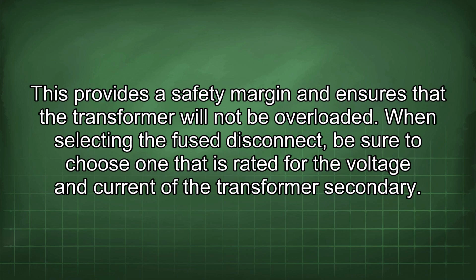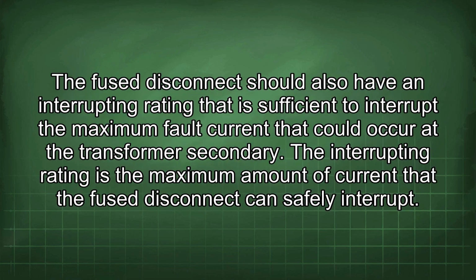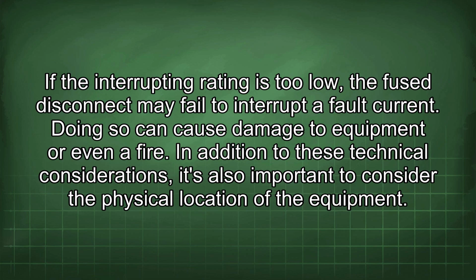When selecting the fuse disconnect, be sure to choose one that is rated for the voltage and current of the transformer secondary. The fuse disconnect should also have an interrupting rating that is sufficient to interrupt the maximum fault current that could occur at the transformer secondary. The interrupting rating is the maximum amount of current that the fuse disconnect can safely interrupt. If the interrupting rating is too low, the fuse disconnect may fail to interrupt a fault current. Doing so can cause damage to equipment or even a fire.